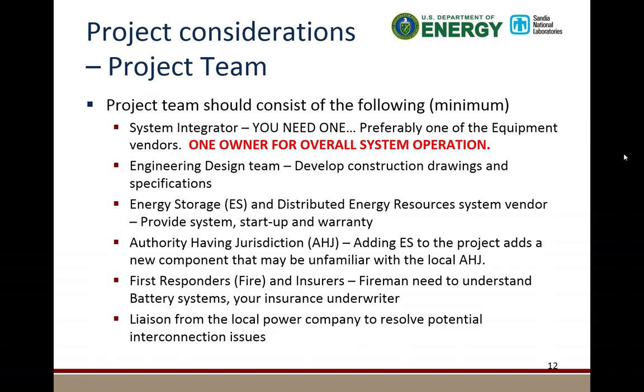So the project team: system integrator, probably the most important part of your team. You should have one that's going to integrate the entire system. Your design team to develop your construction drawings, obviously your vendors that will provide the system, the startup, the warranty and service, your authority having jurisdiction. If you have something out of the ordinary, they're not used to seeing it, bring them in, get them involved at the get-go. It'll be a lot less painful for you than when you're done. You call in the inspector, they're looking at something they've never seen before, and it doesn't pass inspection. Same thing with the first responders and your insurance man, right? We're hearing from firemen that say, hey, we need to understand how to deal with these battery systems in the event of emergency. Your insurance underwriter needs to give you a policy. He needs to understand what it is you're doing. And then you need your local power company to look at the interconnection items.